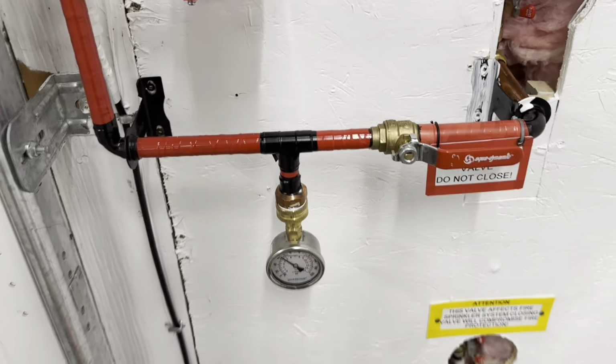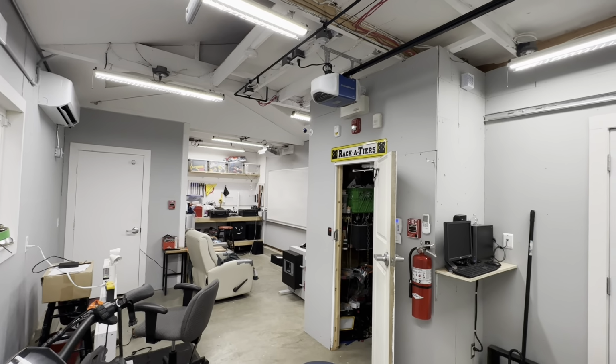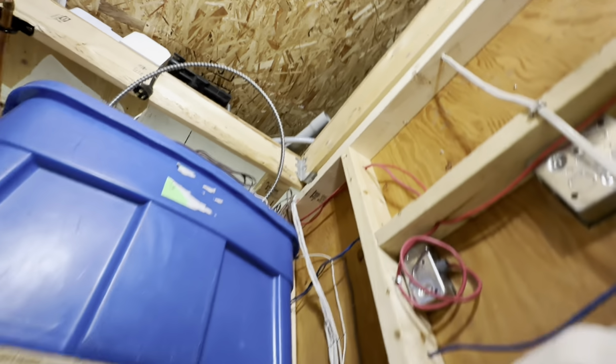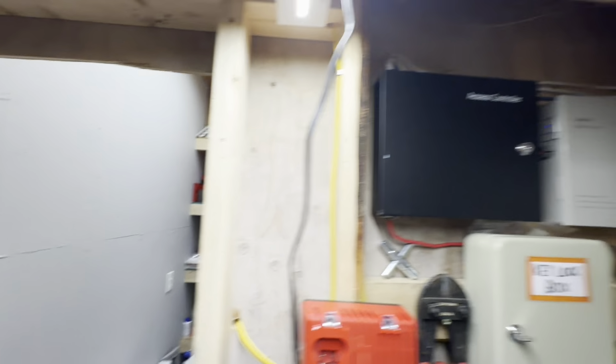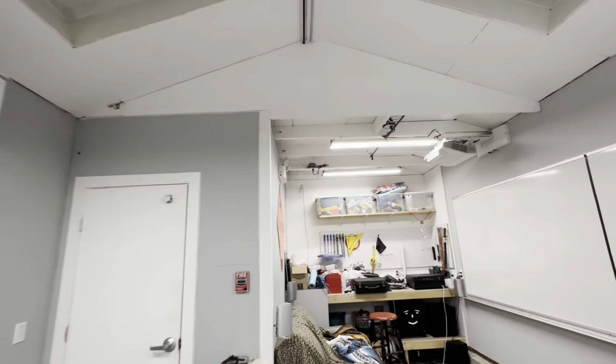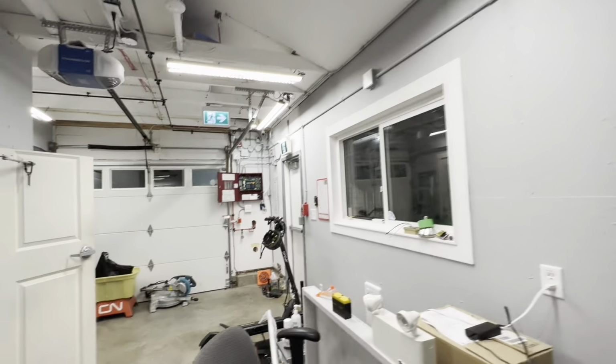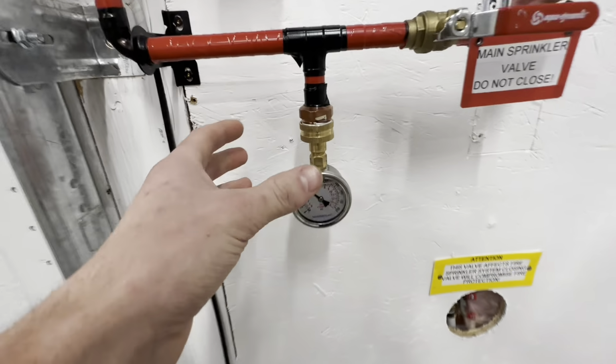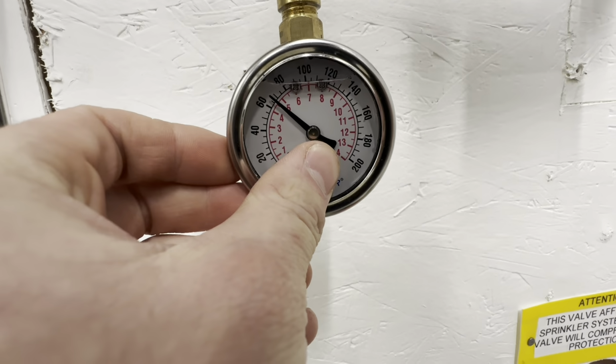Water flow tripped. And, yeah, no sprinkler heads are activated. I suppose I should double check. Think I would hear it and see it. I don't see any waterfalls or indoor water features, and I don't hear it. And the pressure is holding at 70, which it wouldn't be that high if something was activated. So, yeah, I think we're good.